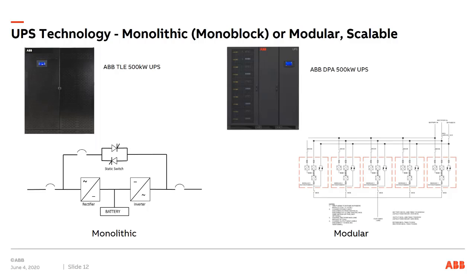So the picture on the right, UPS manufacturers came up with what is today known as modular scalable UPSs, which is essentially installing smaller power modules in a bigger UPS frame. The one shown here is an ABB 500 kW UPS, and the single line shows what it looks like electrically with the doors open. It's 5 small UPSs in parallel.